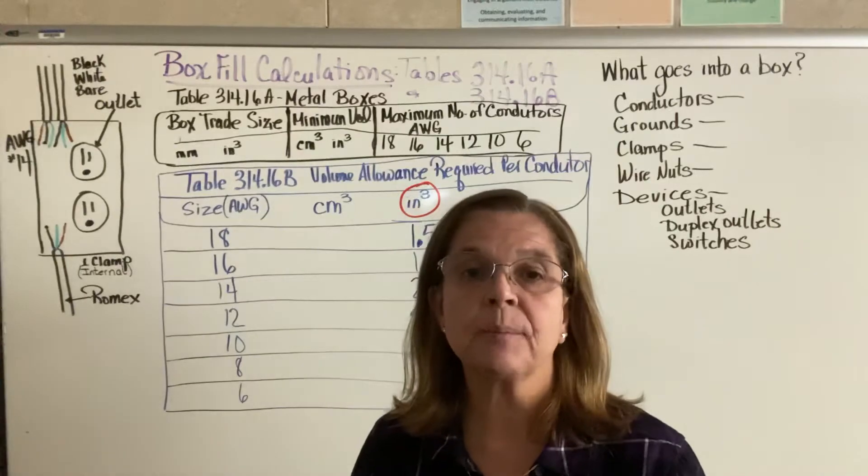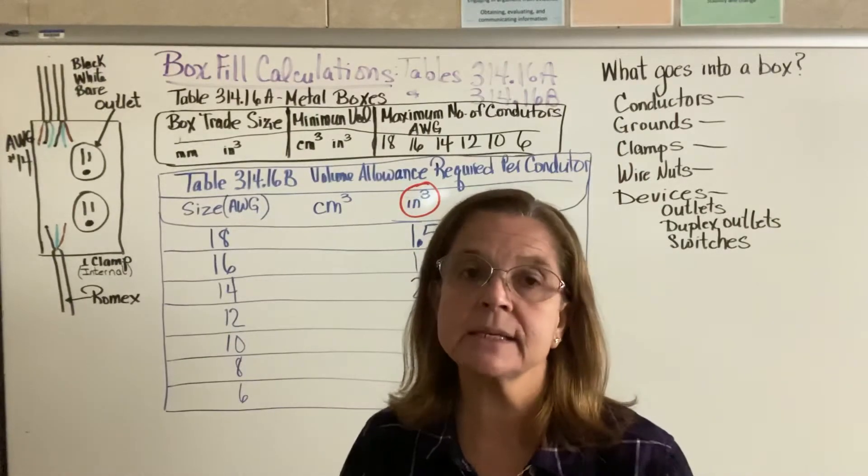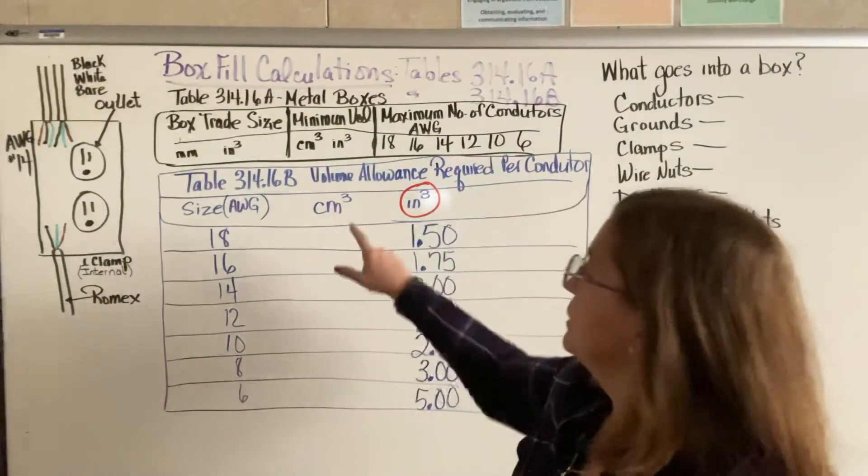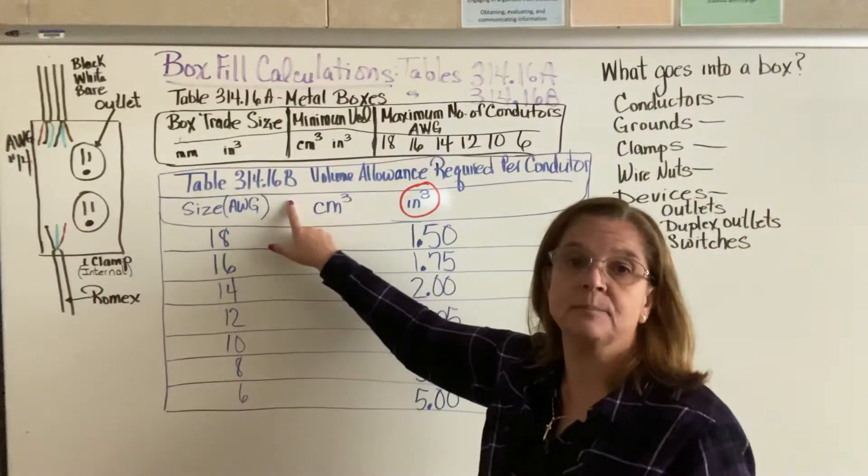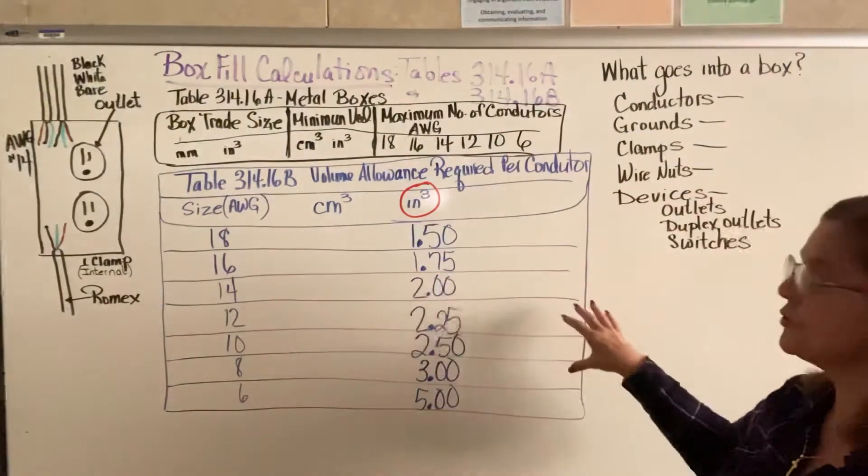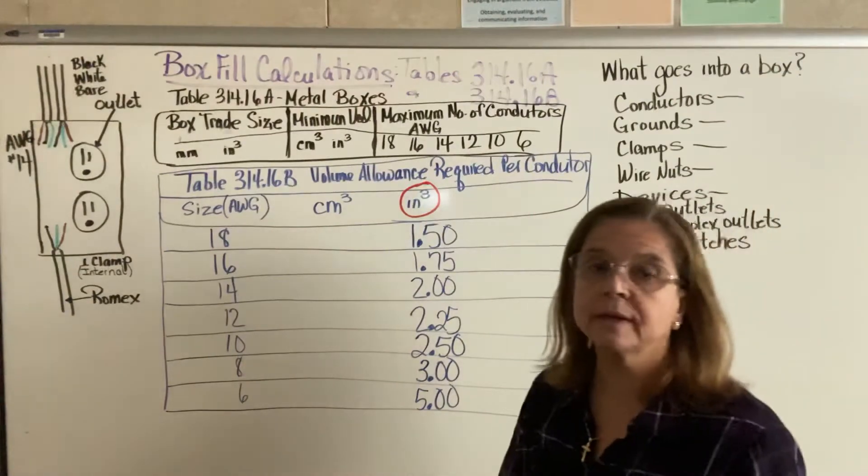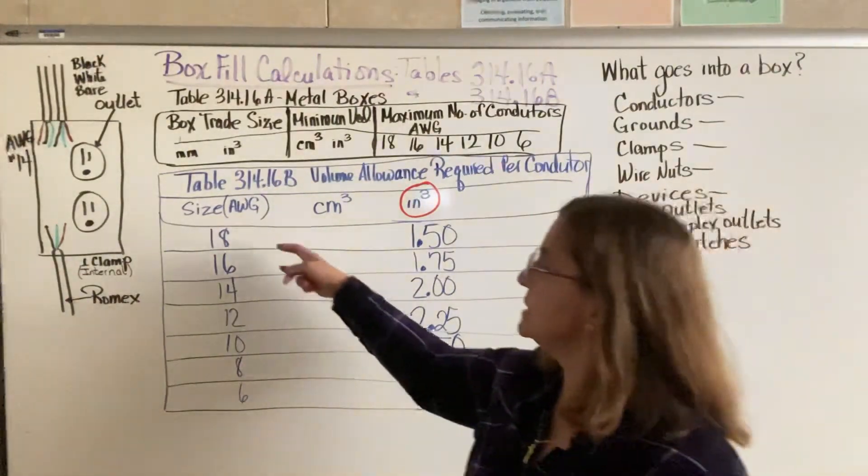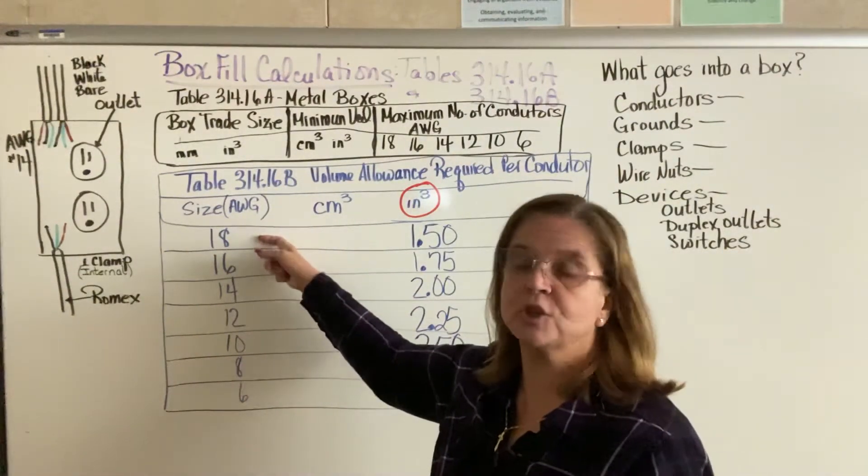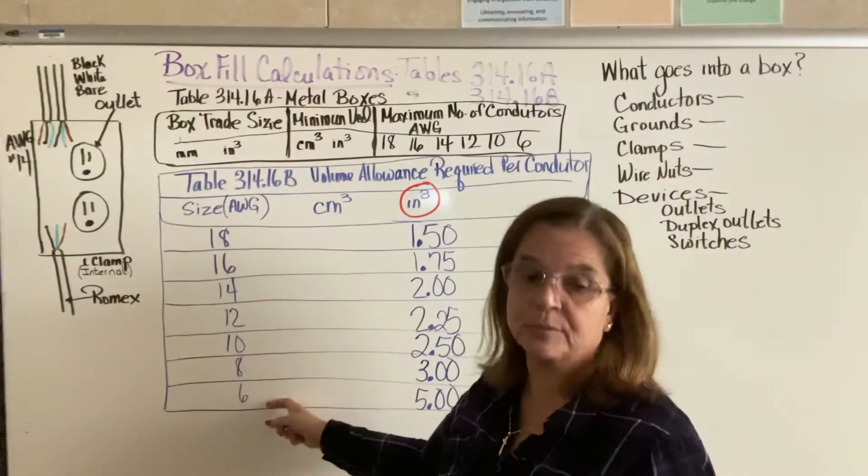What I really want to talk about today is the second table, 314.16B. I pretty much drew most of the table out for you here. It starts at size 18 AWG and goes down to number 6.